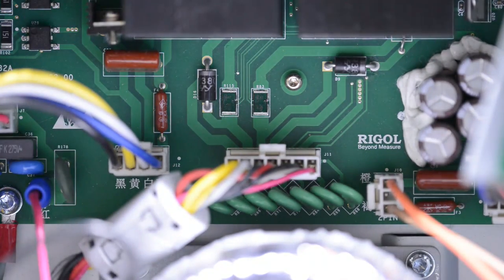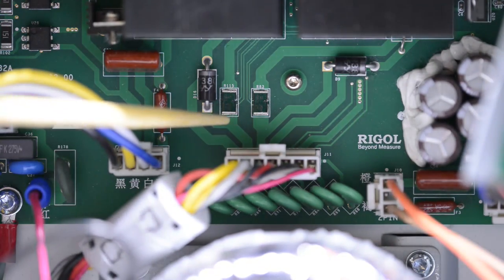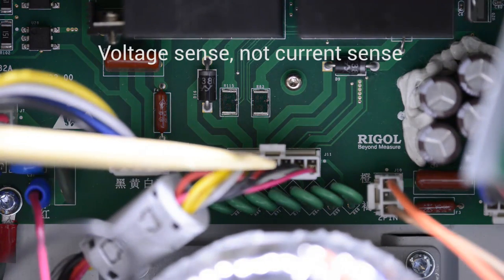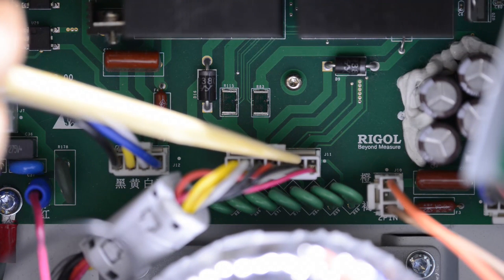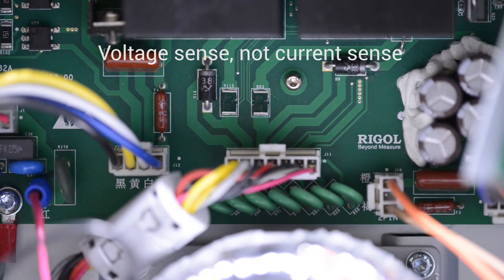So the shorting between the two channels, what's forcing those channels to be common, is obviously on this side of the plug. And in fact, the reason that the two channels are shorted is the current goes from this point here up through the gray cable, right over to the front terminal, back along the gray voltage sense wire here, into the second to last crimp here. And then it's crimped onto the black voltage sense wire, flows all the way back out to the front terminal, and then finally back along this black power cable here, to that point here.